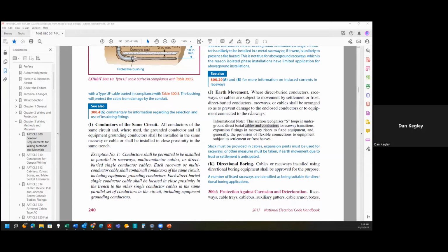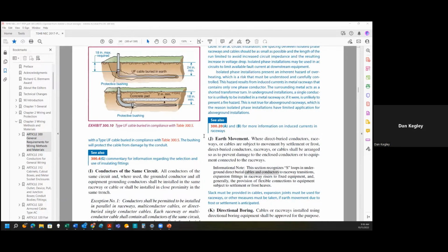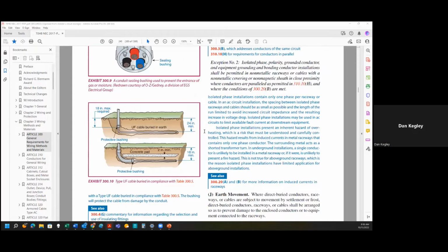Huh. Makes sense. And so expansion fittings can be used, slip sleeves can be used. So there's a variation of products out there that can be used to help compensate for that earth movement. So there's a little tidbit on that, because sometimes we don't see that very well when they just cut a piece of conduit and stick it in the ground and walk away. Well, they should have a slip sleeve, which can be like the next size conduit up that actually goes into the ground. So if this was a 2-inch conduit going into the ground, you could basically stop at ground level with that 2-inch, and you could have a 2.5-inch in the ground, say 12 to 18 inches, and then this 2-inch will just slide inside that 2.5-inch that's in the ground.